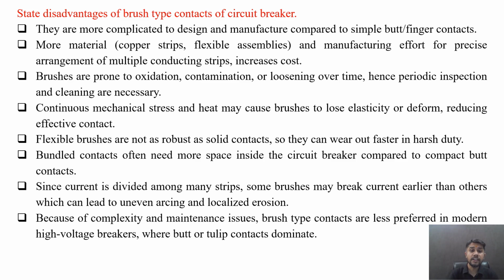Bundle contacts often need more space inside the circuit breaker compared to the compact butt type contacts. Since current is divided among many strips, some brushes may break current earlier than the others, which can lead to uneven arcing and localized erosion. Because of the complexity and maintenance issues, brush type contacts are less preferred in modern high voltage circuit breakers where butt or tulip type contacts dominate. So these are several disadvantages of brush type contacts of circuit breakers.